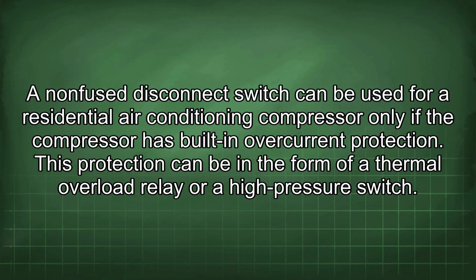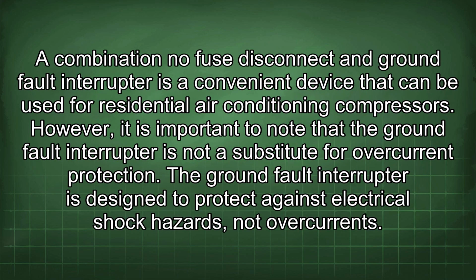A non-fused disconnect switch can be used for a residential air conditioning compressor only if the compressor has built-in overcurrent protection. This protection can be in the form of a thermal overload relay or a high-pressure switch. A combination no-fuse disconnect and ground fault interrupter is a convenient device that can be used for residential air conditioning compressors. However, it is important to note that the ground fault interrupter is not a substitute for overcurrent protection. The ground fault interrupter is designed to protect against electrical shock hazards, not overcurrents.